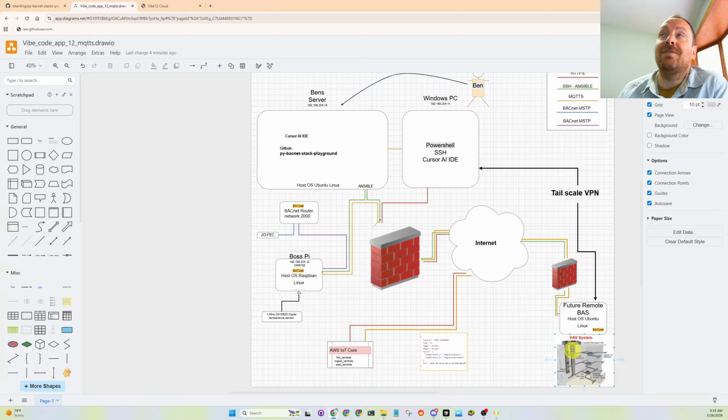So for example, if there were 20 VAV boxes and each VAV box could contain 70 BACnet points, we probably only need 4 or 5. That's only 10% of the points in the building automation system that are useful for fault detection purposes. I'm only going to scrape the bare minimum, probably at 1-minute polling. We could even do 5-minute polling too.